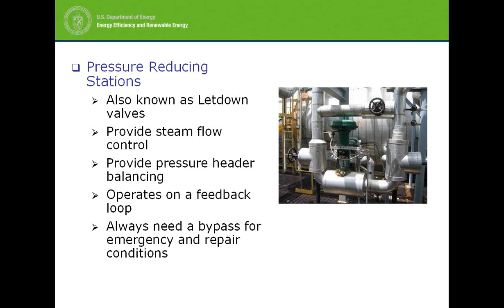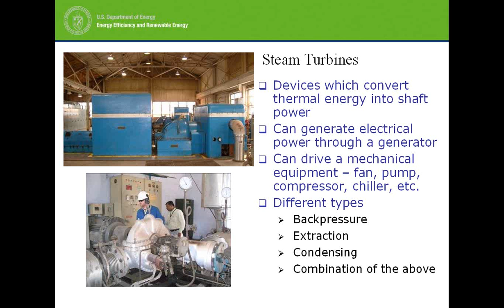We try to evaluate that using our plant as a basis. We have steam turbines. Some of you may not deal with these at all, others may be dealing with this all the time. They are devices which convert thermal energy into shaft power. That power can go through a generator for electrical power, or drive mechanical equipment like a fan, pump, compressor, or chiller. There are different kinds of steam turbines, and depending on the application and need, you may or may not end up using turbines at all.